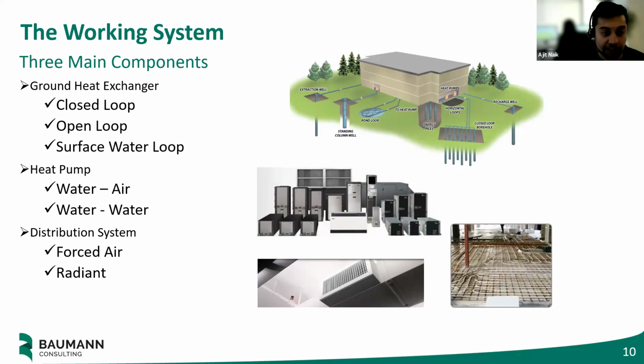So regardless of the application - whether it's a single family home putting in a residential scale geothermal system, or a massive university campus putting in a giant geothermal system to serve the entire campus - these components remain the same. There's always a heat exchanger buried underneath the ground. There's always a refrigerant-based heat pump that takes that water and either uses it to generate hot air or hot water, or cold air or cold water. There's some kind of distribution system - like a typical air handler or pumps that distribute that heating or cooling air or water throughout the space.